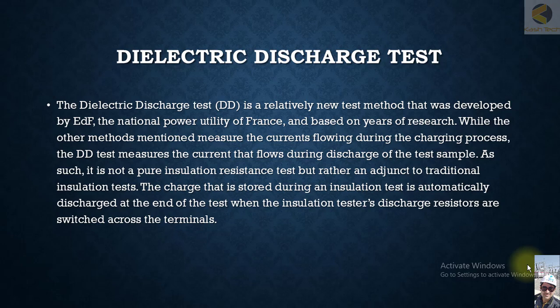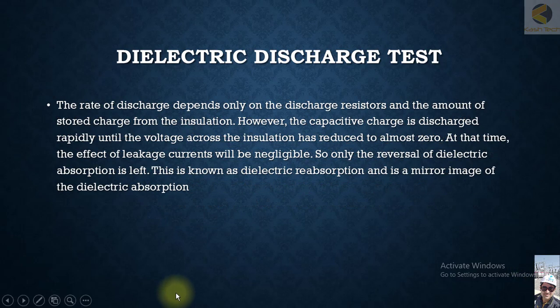In normal testing, once the cable or equipment is fully charged, you take the reading, then disconnect and discharge the equipment. But with the Dielectric Discharge Test, all measurements and currents are taken while the equipment or cable is discharging. The rate of discharge depends only on the discharge resistor and the amount of stored charge from the insulation.